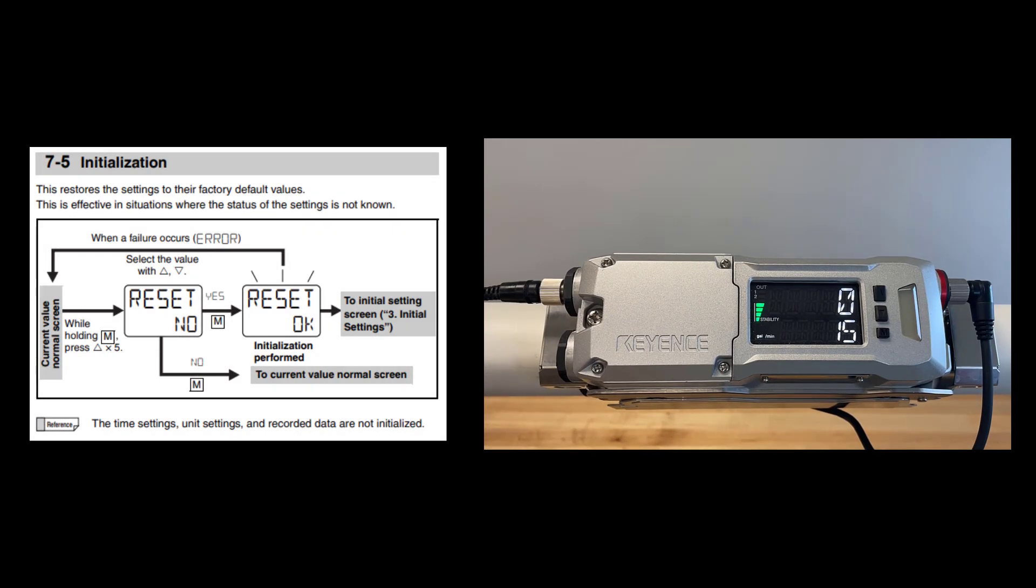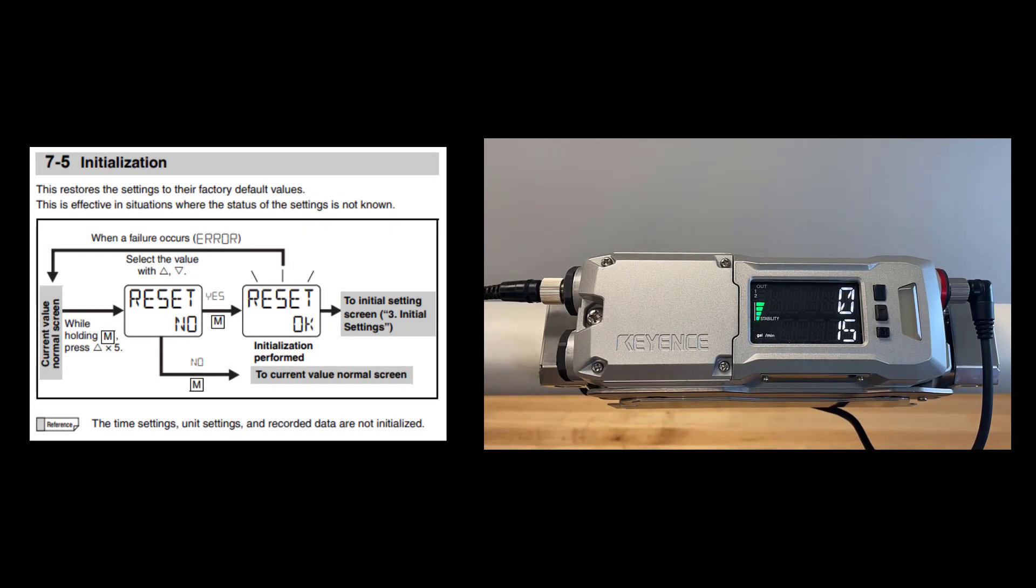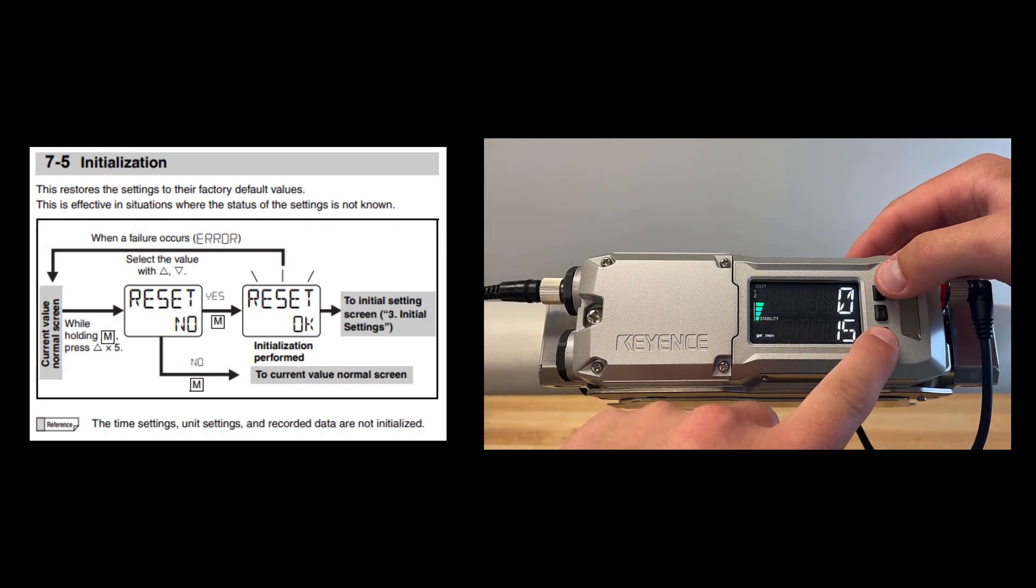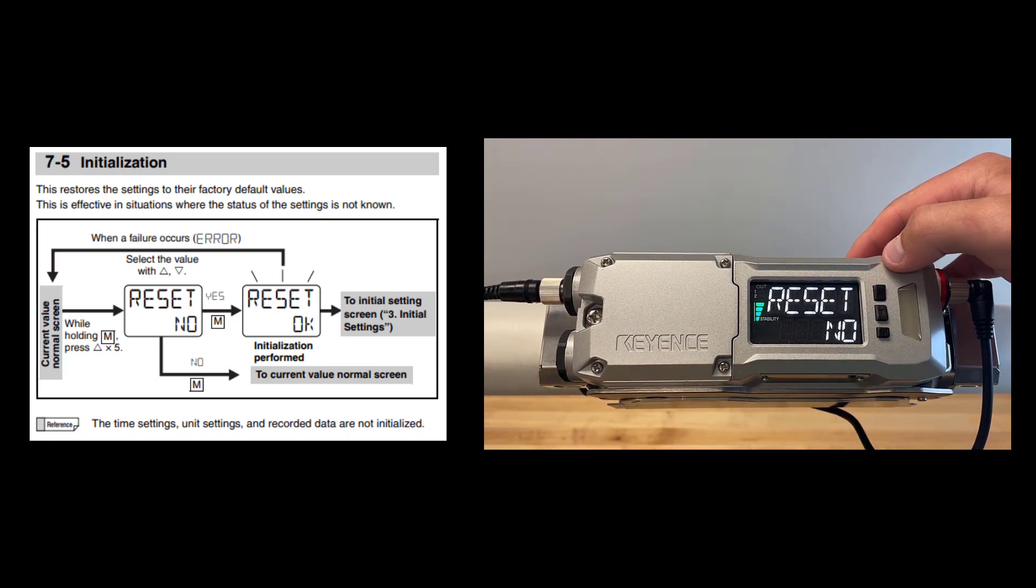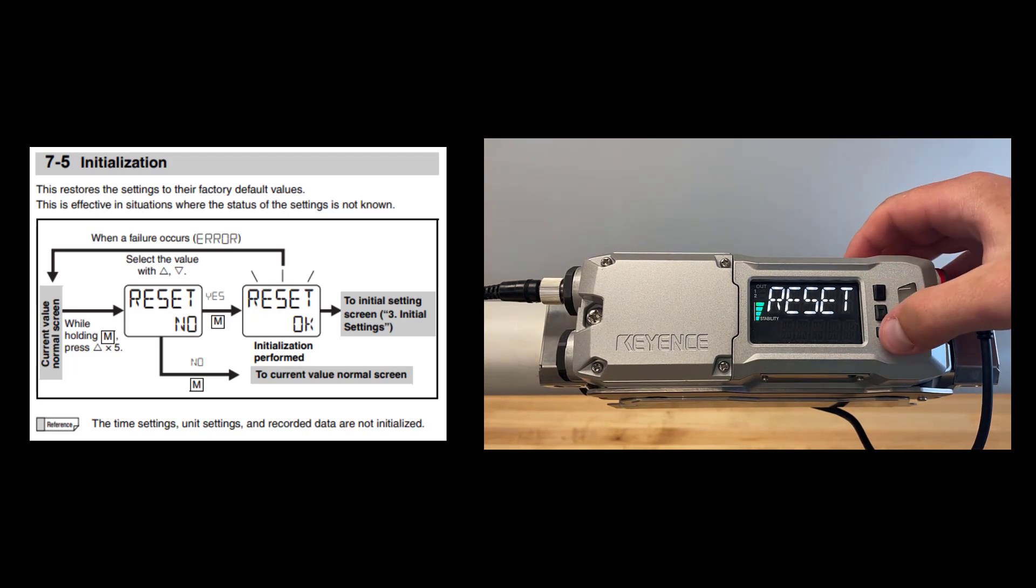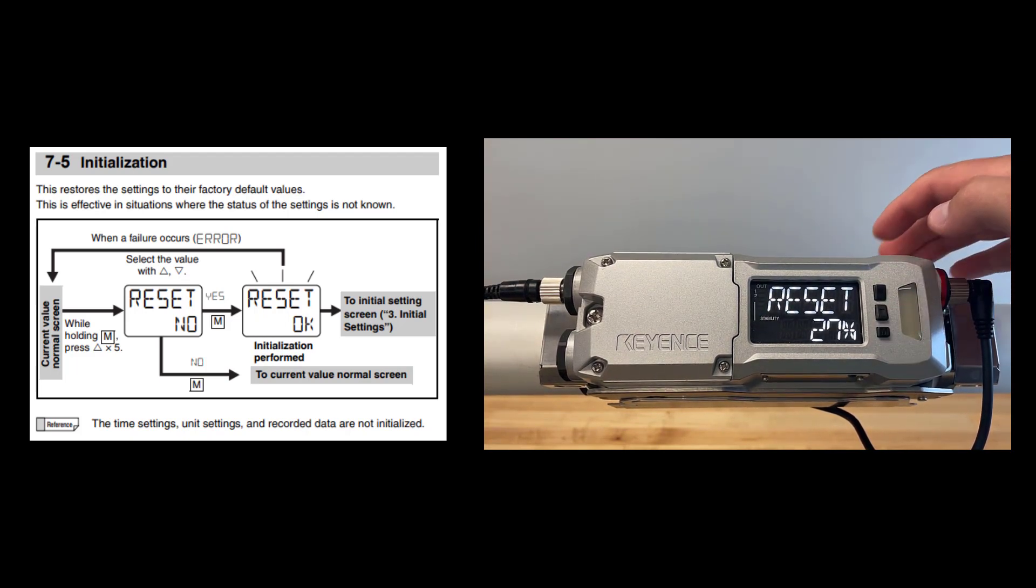If at any point you need to change or modify any of those initial settings, hold mode and tap the up arrow key five times. Reset should be displayed. Tap the up arrow once to cycle to yes, and tap the mode button one more time to initialize and bring the unit back to a factory default state.